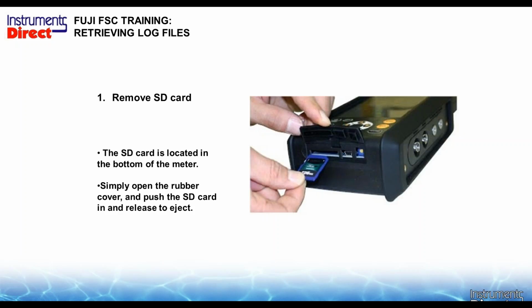So the only meter out there that has a large data storage is the Fuji, which has a couple gig SD card, and you can store data until the cows come home. Remember, each data point, each item is a data point. So if you were just logging one data point like flow, once a minute, it's 1,440 data points in a day. Then you want to add temperature times 2. You want to add the other temperature times 3. You want to add the BTU and other outputs for BTU. You could have a half a dozen points per minute. So you can see you can eat up data very quickly in energy management applications.